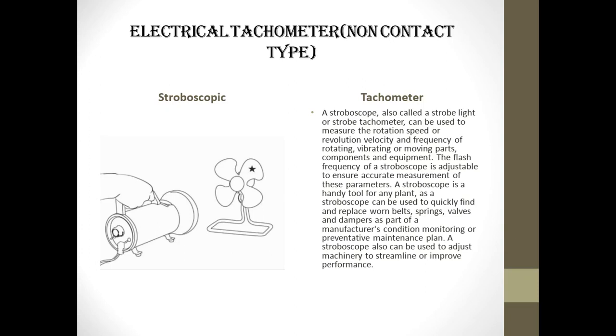The speed is measured by adjusting the frequency so that the moving objects are visible only at a specific interval of time. The method used in the stroboscope depends upon the imperfect dynamic response of the human eye. If a strong light is caused to flash on a moving object which at the time of each flash occupies a given position, the object will appear to be stationary. Therefore, the method is useful for only those types of motion which occur regularly after a fixed interval of time, such as oscillation or rotation.